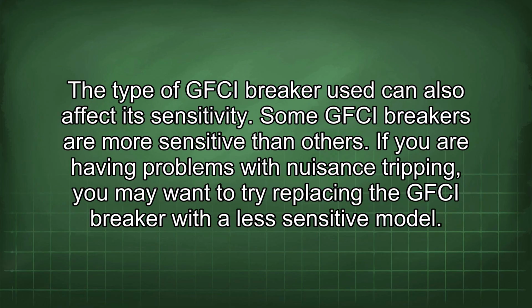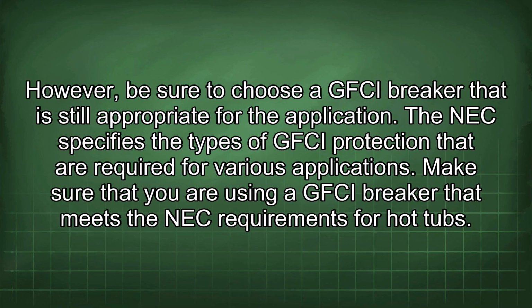The type of GFCI breaker used can also affect its sensitivity. Some GFCI breakers are more sensitive than others. If you are having problems with nuisance tripping, you may want to try replacing the GFCI breaker with a less sensitive model. However, be sure to choose a GFCI breaker that is still appropriate for the application. The NEC specifies the types of GFCI protection that are required for various applications. Make sure that you are using a GFCI breaker that meets the NEC requirements for hot tubs.